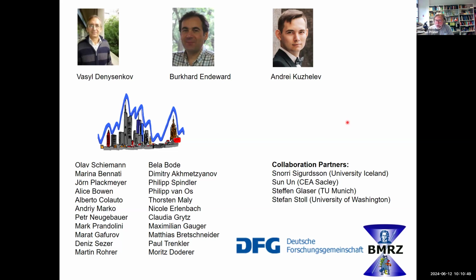Now, still, this is critical, because if something happens within the experiment, your interferometer, for some reason, displaces some micrometers, you destroy your microwave detector. Just as a joke, that's what we're doing at the moment regularly with Bruker low noise Q-band detection amplifiers. We destroy them like fuses. Every 3 weeks we get a new one for free from Bruker because something is going wrong. But that's not really what you want to do.